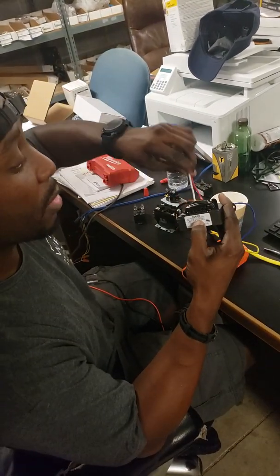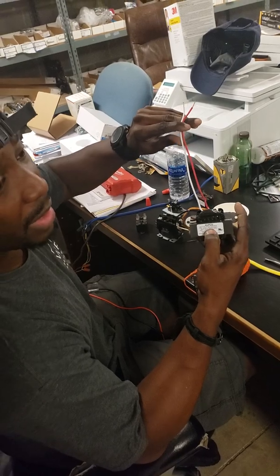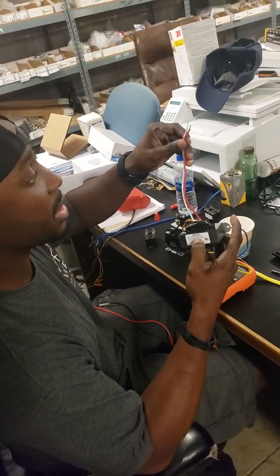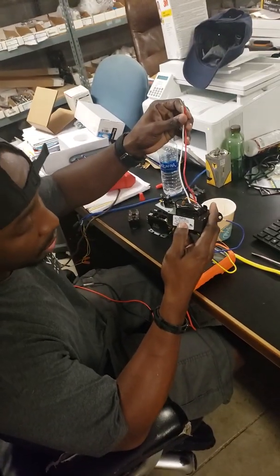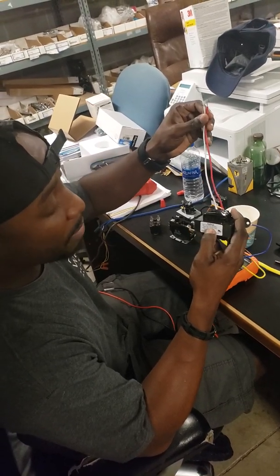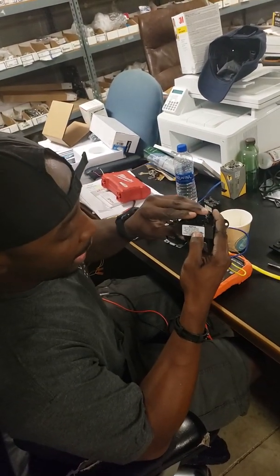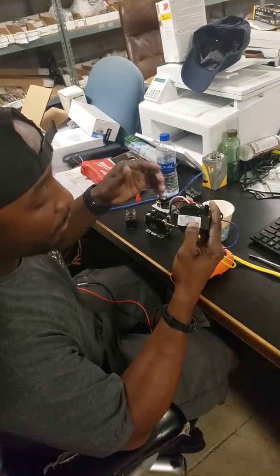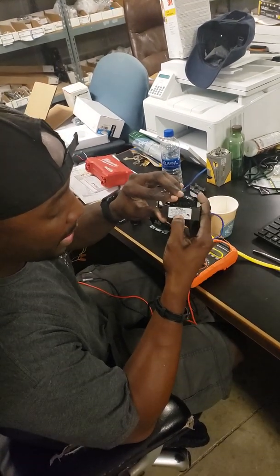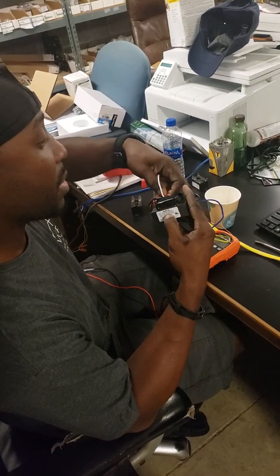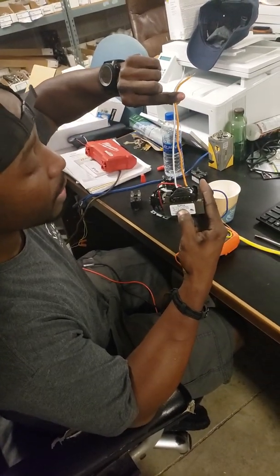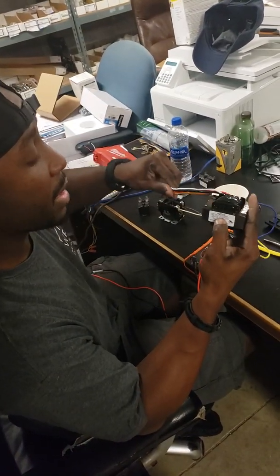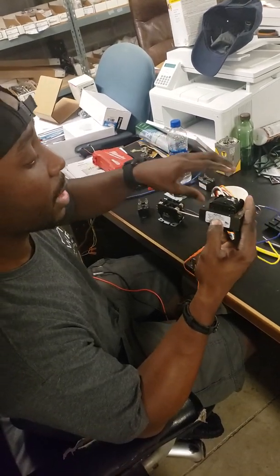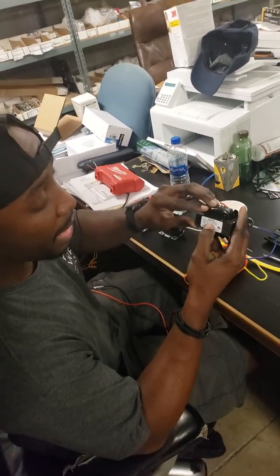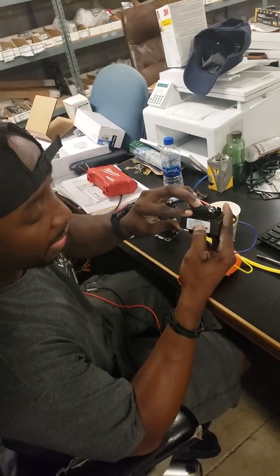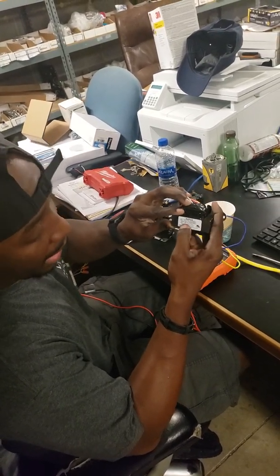If I was hooking up something that was 208 volts, stuff that runs off of 208 volts is like dryers, some washing machines, things like that, you will hook these two wires up to step that down to 24 volts. And lastly, if you had something that was 240 volts that you were stepping down to 24 volts, you will hook up these two wires right here. Okay, so this is a multi-phase transformer that can step down 120 volts, 208 volts, or 240 volts down to 24 volts.